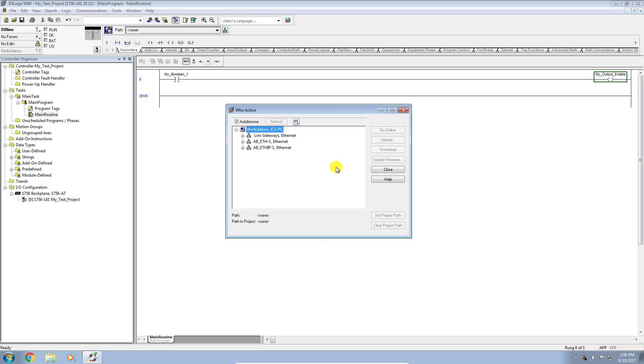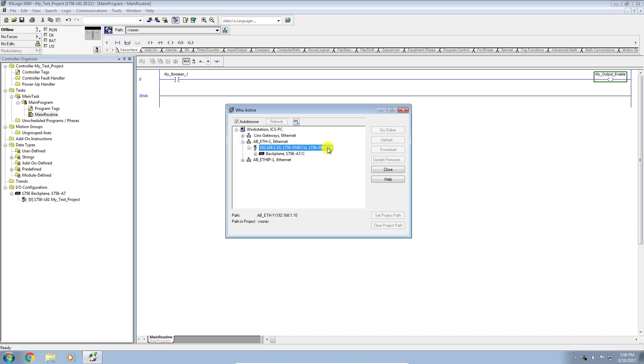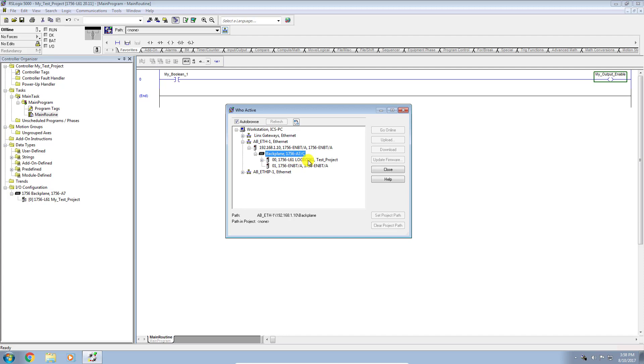So I'll just choose this Ethernet1, which is an Ethernet devices driver. And you can see here, my Ethernet bridge module is currently configured at the 1.10 address, like I had said previously. Okay, so I'm going to drill down, get to my backplane. And then now I can see everything that currently resides in this chassis. I want to download to the CPU, so that means I need to select the CPU. And then I will click Download.